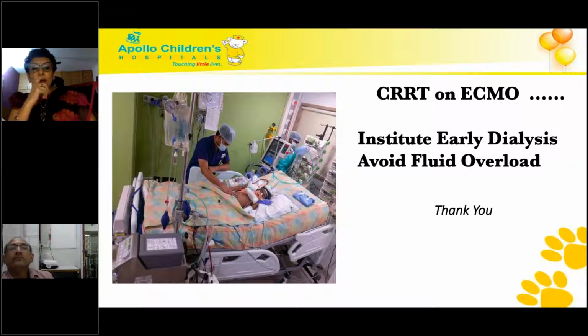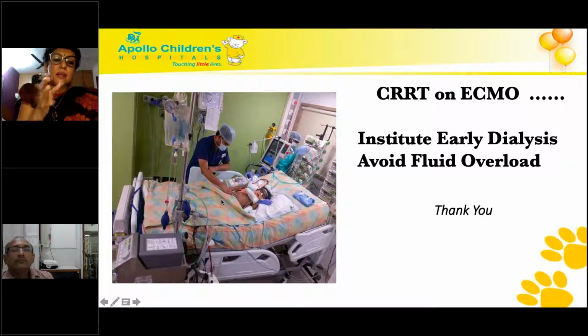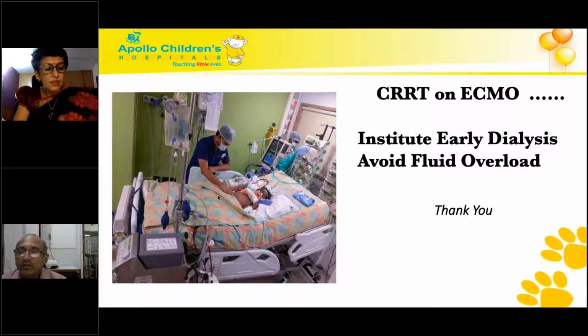Yeah, I got what you mean. Correct. But our perfusionists have more experience managing the pressure differences, and they found that with this approach they have the fewest complications and the filter also lasted longer. Dr. Pranay, what is your opinion? Usually we do the same way. We take the access from the post oxygenator and give the return to the pre-pump. So that is from the positive pressure to the negative pressure. Plus the air going in will be minimized, and even if some micro air goes in, it can be captured in the pump or the oxygenator. So nothing goes to the patient at least.